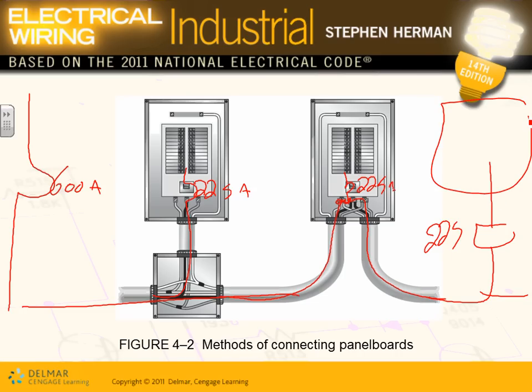So you can take a feeder through a junction box or through a feed-through. This is not feed-through, this is sub-feed, they call it. Through a sub-feed arrangement here, you can feed the panel, go to the second panel. That's one way, guys, of saving some money in the field, where you can have one feeder, tap that feeder to multiple locations. Obviously, there are rules for tapping when you go from here to here, so you have to stay within either the 10-foot rule or the 25-foot tap rule when you tap that feeder.